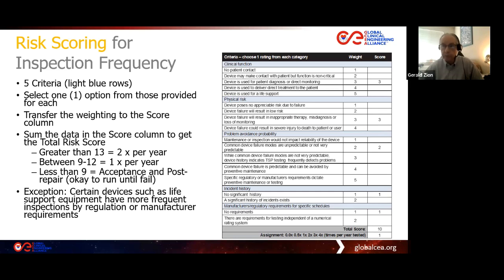And the way we use this total risk score is, if the total risk score is greater than 13, then we will apply a 2 times per year inspection interval. If the total risk score is between 9 and 12, that's a low enough risk that we would just inspect and test that medical device 1 time each year.